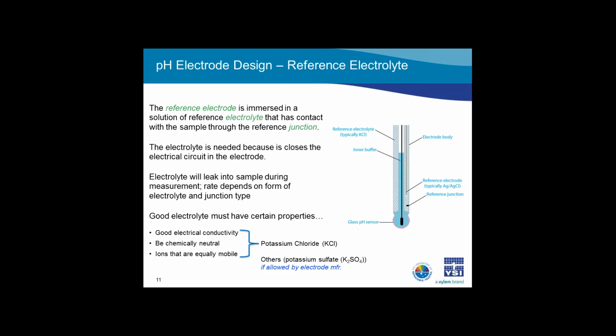A reference electrolyte must have certain qualities. It must have good electrical conductivity, and since some electrolyte will leak into the sample during measurement, it is also important the electrolyte not react with the measurement solution. The ions of an electrolyte solution must also be equally mobile. If they aren't, unwanted potentials can develop, resulting in poor results. Potassium chloride, or KCl, has all of these qualities, so it is by far the most commonly used electrolyte solution.